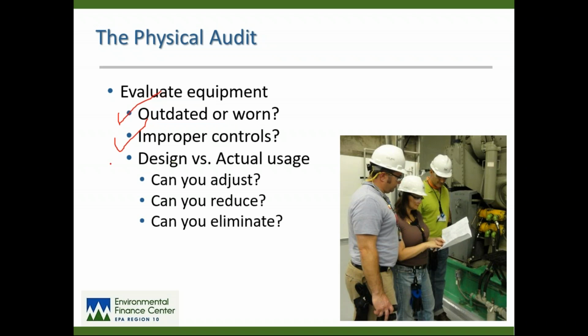Then we want to evaluate what the engineer gave us in terms of design versus how it's actually being used. Can we adjust something to reduce energy use? Can we reduce something? Can we turn a pump off at certain times? If you're on time of use energy metering, can we have all of our large loads running when energy costs are inexpensive, and turn all those off during peak energy rates? Can you eliminate something? Eliminate a pump, eliminate a light.